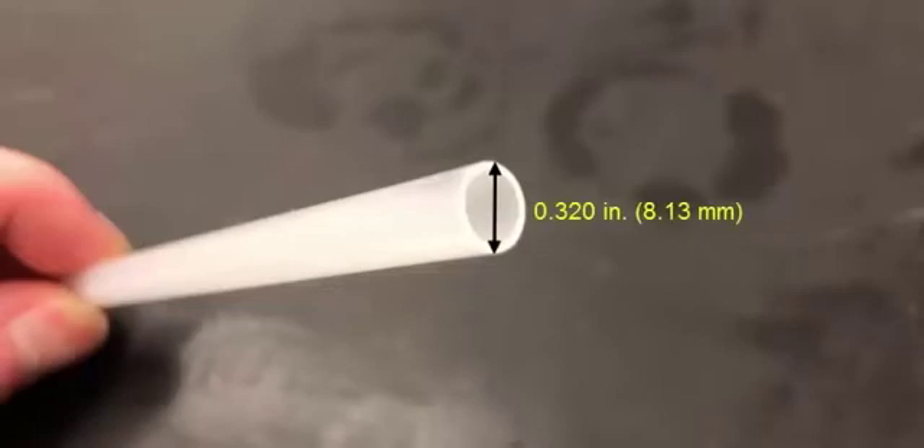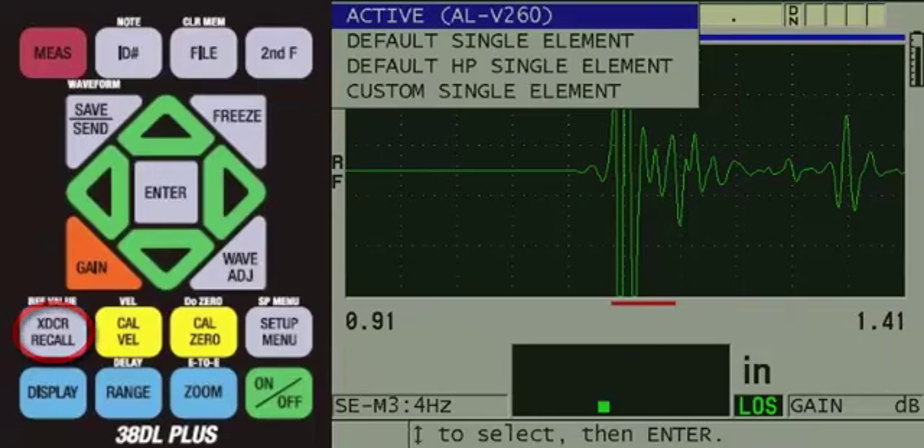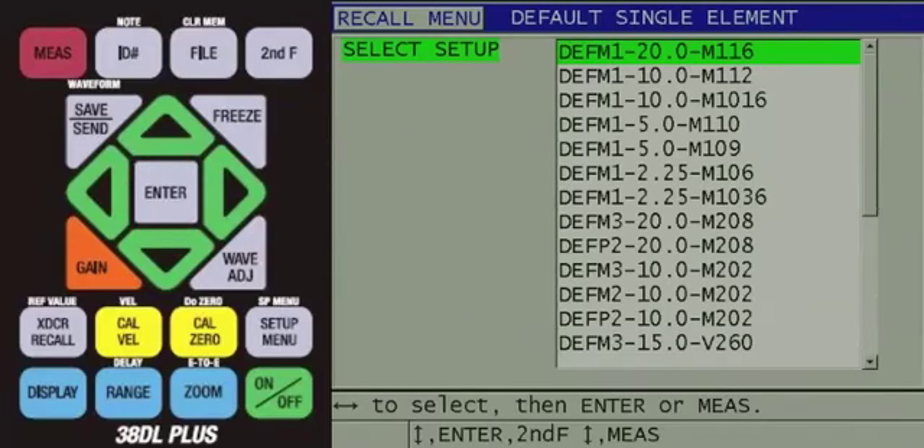We will now show how to set up the V260-SM Sonopen delay line transducer to make measurements on a 0.320-inch or 8.13-millimeter diameter plastic tubing sample with a wall thickness of 0.029 inches or about three quarters of a millimeter. Since this is also a tubing sample, we will once again use the spring-loaded V-notch holder. The first step would be to press the XDCR recall key. Since we are using a 15 MHz transducer, we will press the down arrow to default single element and then press ENTER. Since plastic does not produce strong multiples, we will be unable to make a MODE 3 measurement and will therefore want to make a MODE 2 measurement. So we will press the down arrow to highlight DEFP2-15.0-V260.